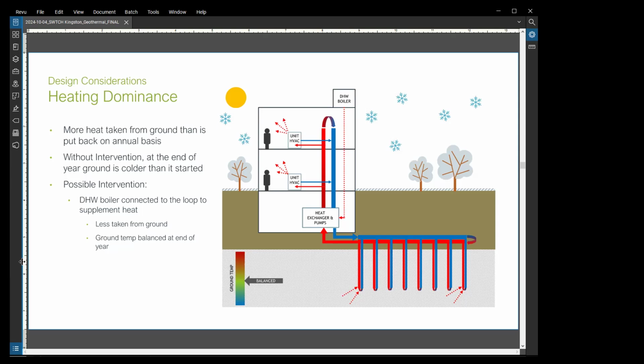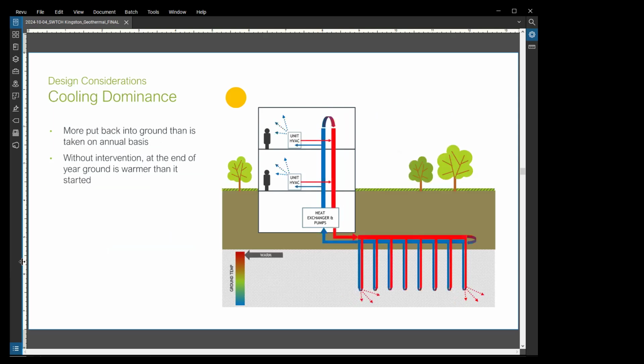It's not perfect, but when you're looking at the metrics of your project, another question is how often this boiler will actually come on. It's not an everyday thing, it's more that you're monitoring your well temperature over a couple of years and you decide you need to run this boiler for 3 days to bring up the temperature, then turn it off again. All of those things need to be considered when figuring out the best approach for adding heat to the loop.